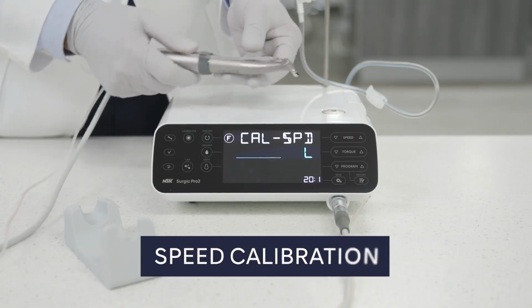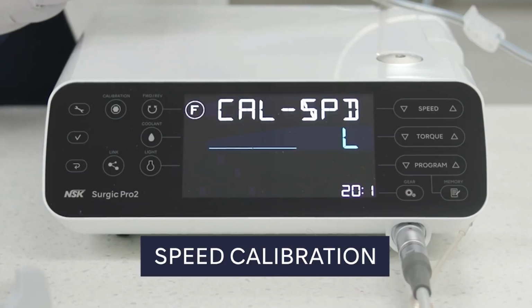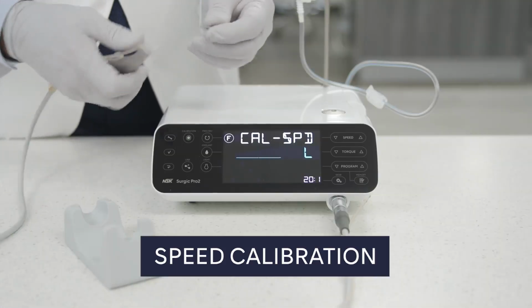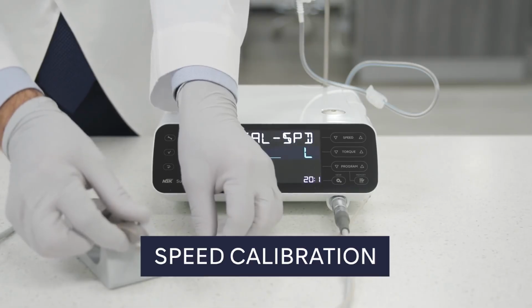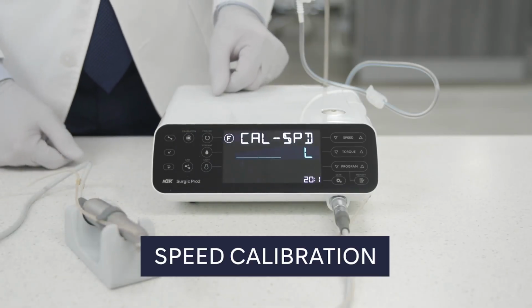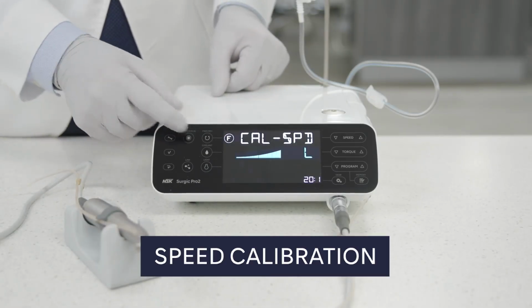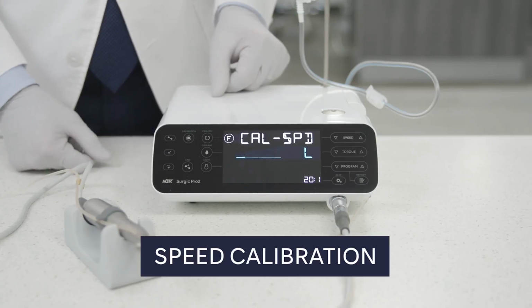And for speed calibration, an L is shown on the display. Remove the burr from the calibration block and leave the motor and the handpiece on the handpiece stand. Make sure the burr is not touching anything. Press calibration. You will hear a beep sound and the calibration burr automatically spins at a low speed. After another beep, pass appears on the display.